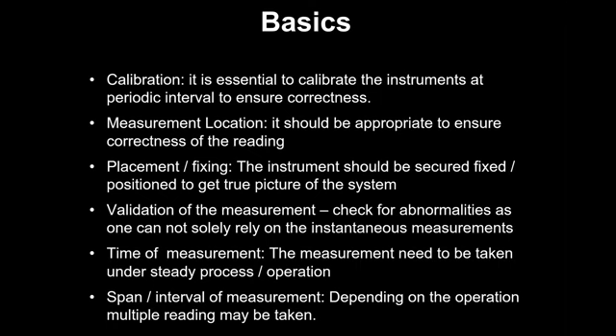But he insisted. We did the measurement, and the pump efficiency was coming out pathetic, around 30%. The flow was coming very low. I told him, anyway, these readings are not reliable; I am doing it because you have suggested. We still called the OEM on phone. The OEM didn't come to the site, but we talked to them. We saw the curve, we saw the power consumption, and nothing was matching. So ultimately we decided, okay, let us do it the other way.